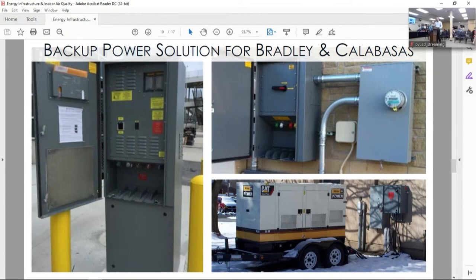So what we've looked at here is a plug-and-play type system using docking stations. Effectively, there's going to be hardwired connections ready at each meter for the two campuses to allow you to bring in a portable generator and immediately plug it in and have power ready to go. As part of this program, we're going to have two portable generators included to power the main meters at each site, so you can start off with those permanently docked there. Then as years go on, this could be a technology to expand to other campuses, providing docking stations there, and those generators can be moved to whatever sites have outages for a relatively cost-effective solution across all your campuses.